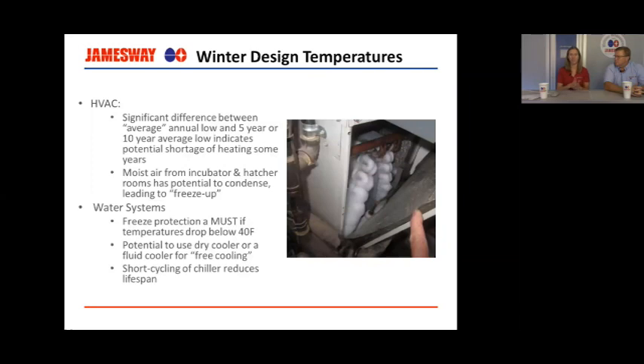Basically, rule of thumb is if your winter design temperature is below 8 degrees Fahrenheit, I'm sorry, I don't know what that is in Celsius, then you are in the area where you're of concern. And of course, the colder it gets, the more concern that we have. The other concern with your winter temperatures is your water systems.